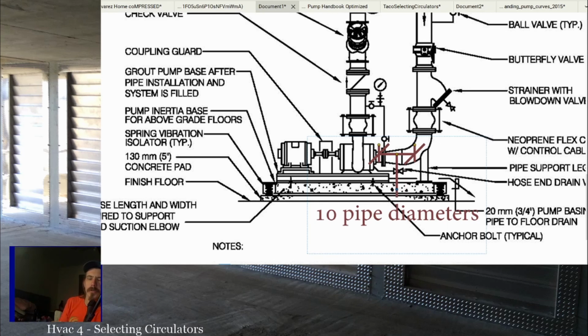If you cannot have the 10 pipe diameters before the pump, and this is very common on large piping, all right? If you cannot have the 10 pipe diameters, you can have what's called a suction, right here, all right, or a suction diffuser.